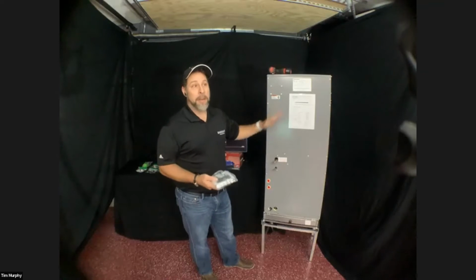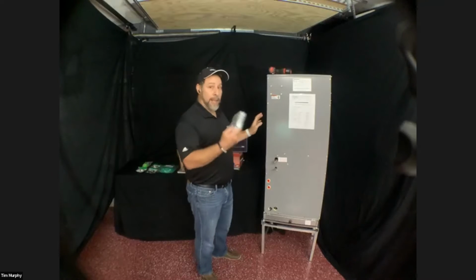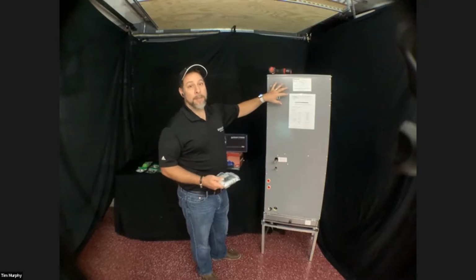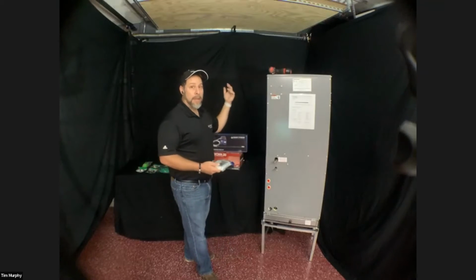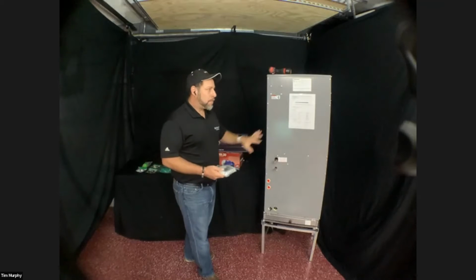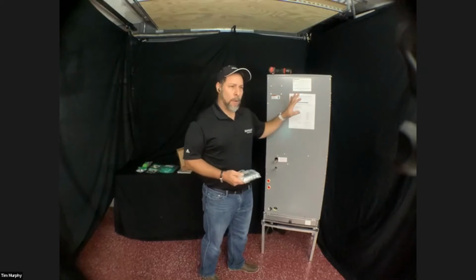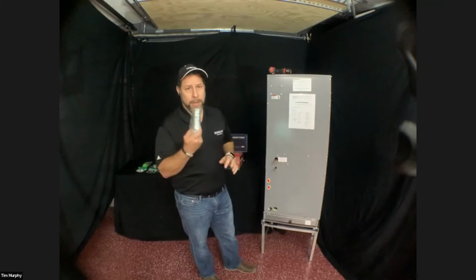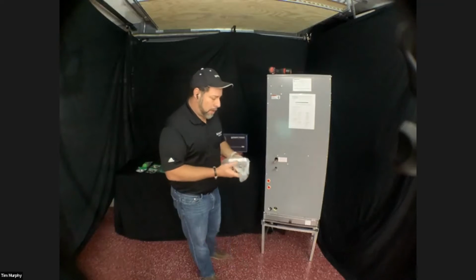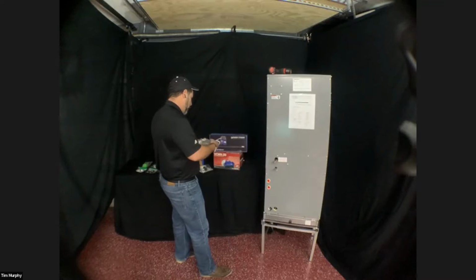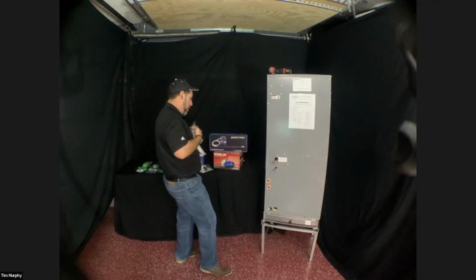Also, with this, you can control a fresh air damper. So if you have a motorized fresh air damper in a commercial setting, you can get into the settings, and there are access points on the board where you'll be able to control that fresh air damper. So like I said, there's a wide range of settings you're going to be able to use, but you really need to use the advanced controller. I will take it out of the bag here real quick and show it to you.